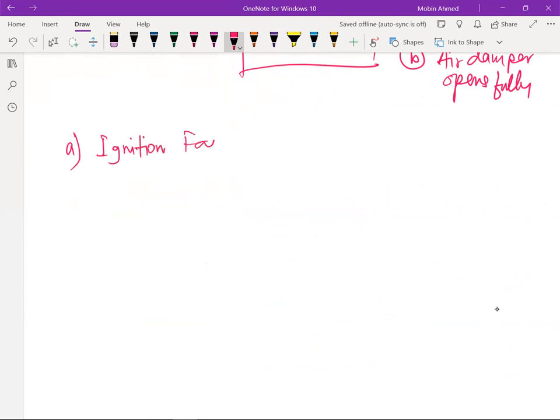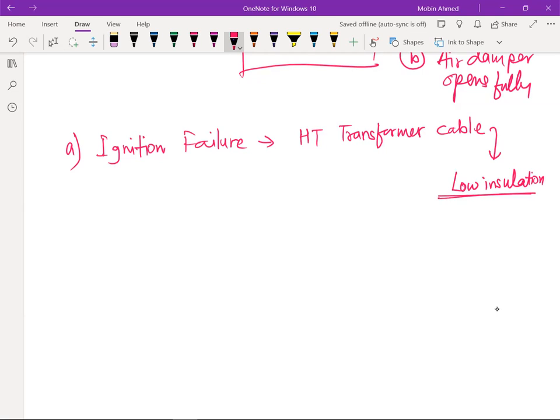The main causes of the ignition failure is the transformer, that is the HT transformer. The chance of the HT transformer being bad is very, very less. But the HT transformer, and the cable, if it has low insulation, this is a problem. That means the spark is not going to be fully there. So the HT transformer plus cable should not have low insulation. Low insulation generally happens when the insulation material breaks down, and the cable which is connecting is also the HT cable.